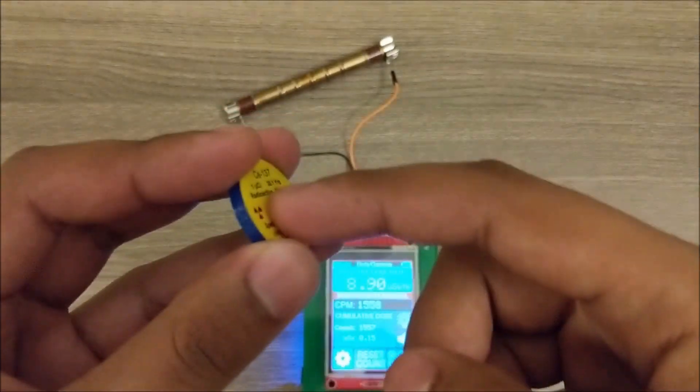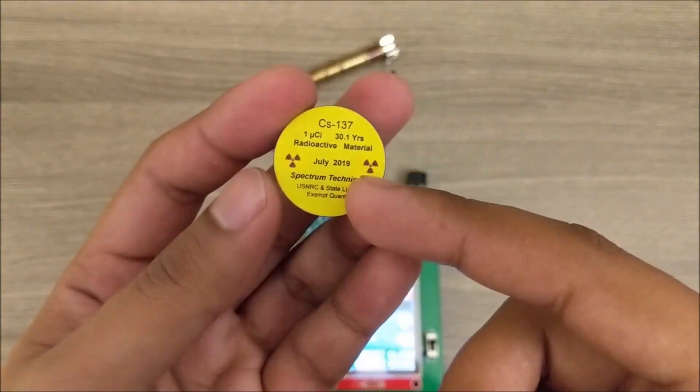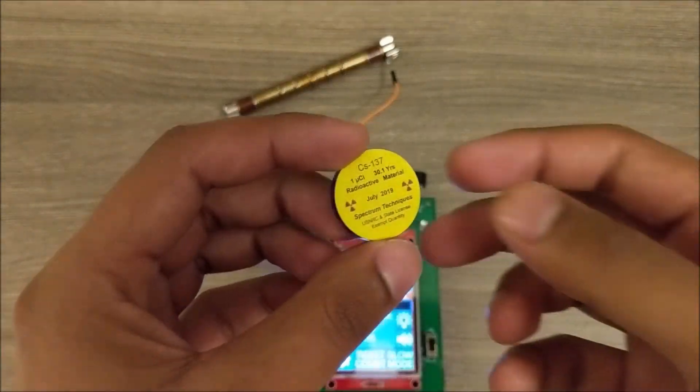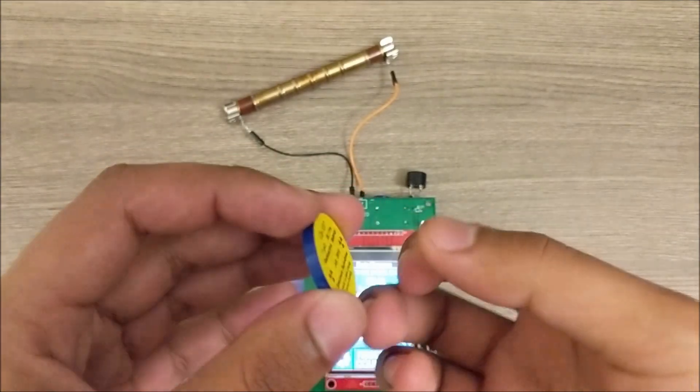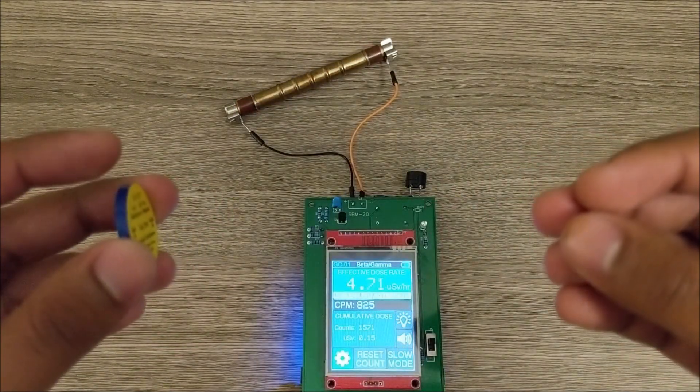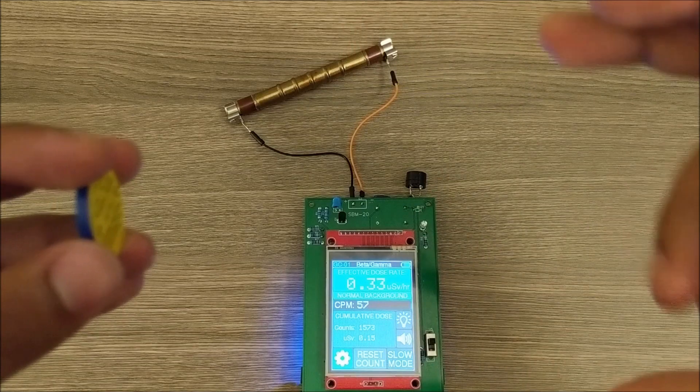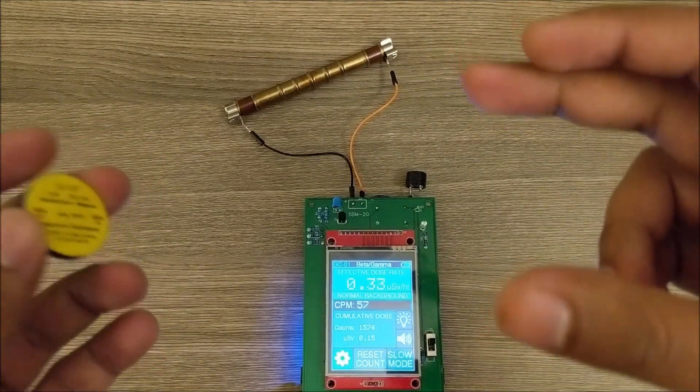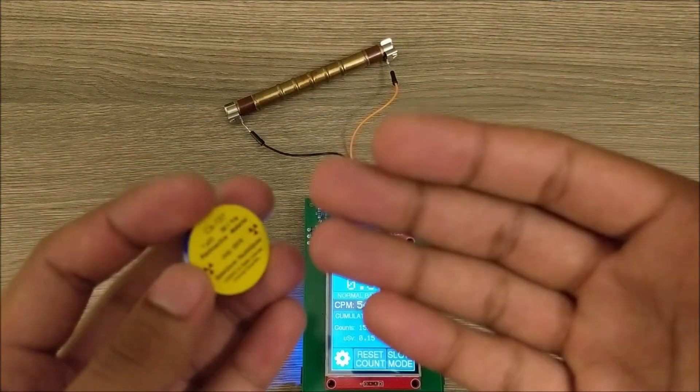The basic idea behind calibrating a Geiger counter is that we take a source and we calculate theoretically using formulas what the effective dose should be at some distance. Then we place the Geiger tube at that distance and measure the counts per minute that it gives us. So then we have an easy way to relate the counts per minute to the expected dose rate at that distance.